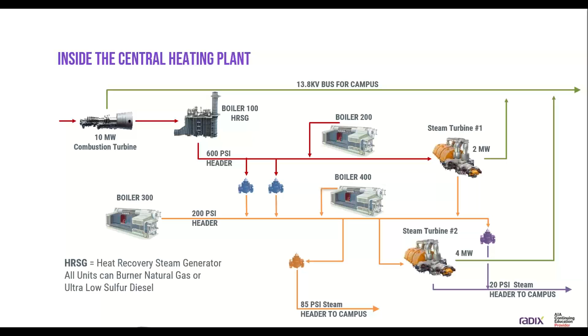This would be one of our 3 package boilers, all designed by Rentech. These all run about 125,000 pounds per hour steam. Once we surpass that, 220,000 pounds per hour of steam, we'll have maxed out that 2 megawatt steam generator you see there. And then we would bring on boiler 300 or 400, which operate at 200 pounds. And these will be supplemental steam for heating season. And we also have a 4 megawatt steam turbine on that. And from there we go to the campus through our 2 main steam lines.